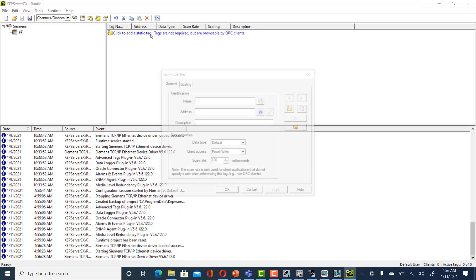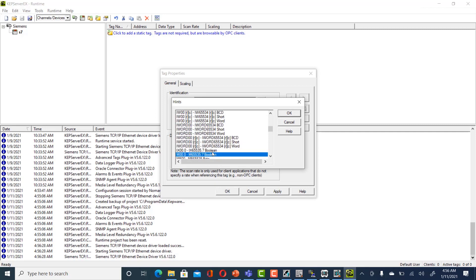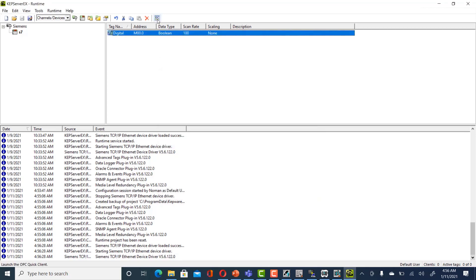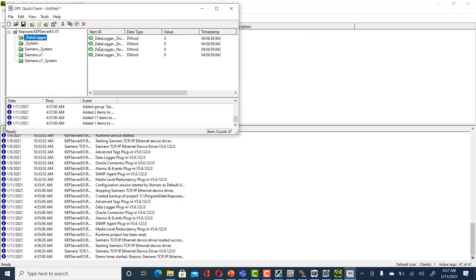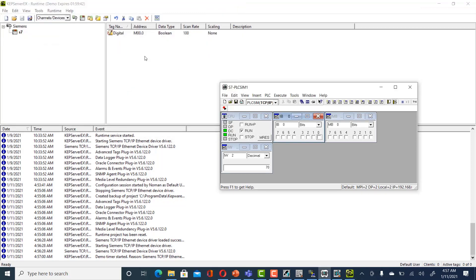To add a digital tag, click 'New Tag', name it 'digital', and set the address to M0.0. Remove any extra options, click OK, apply, and select OK. Open the Quick Client to verify — you should see a boolean value of 1. Toggle it and it should become 0. Confirmed it changes to 0. Now close and add the analog value.